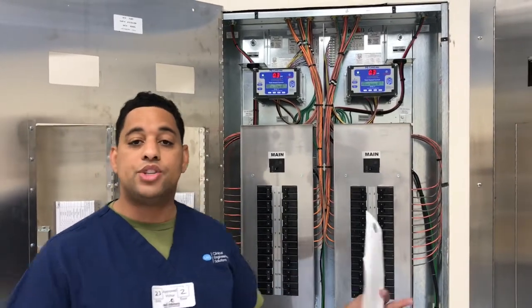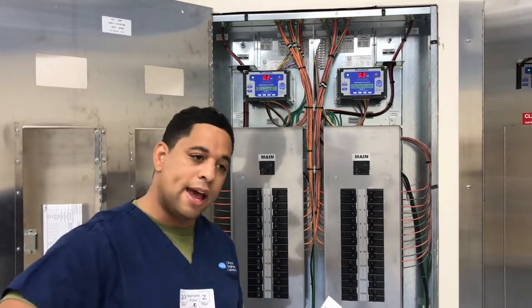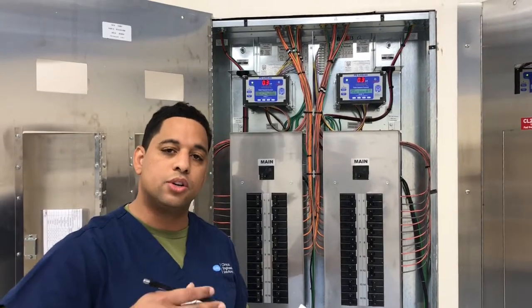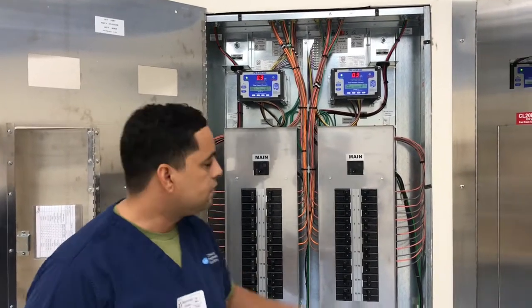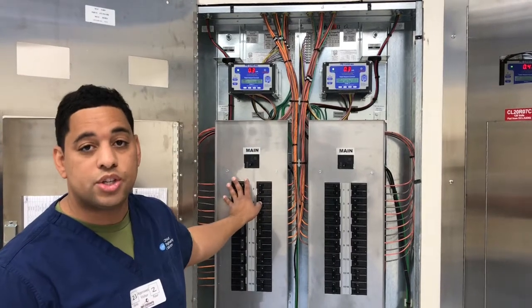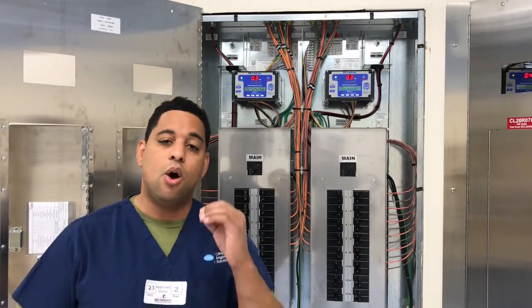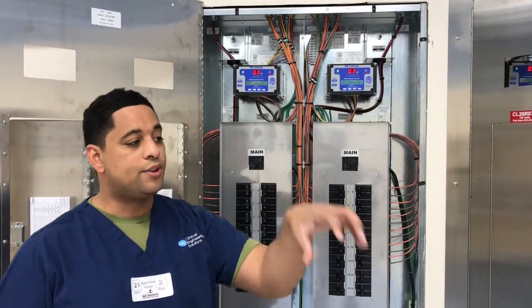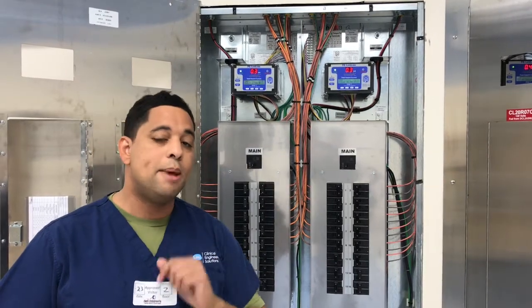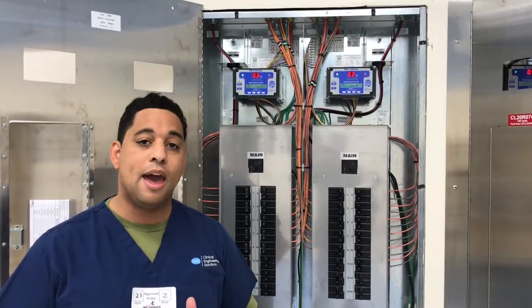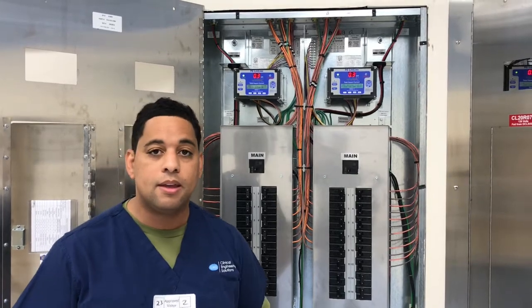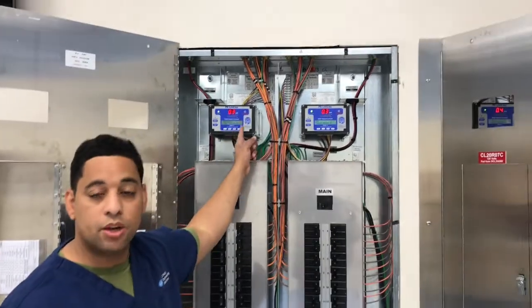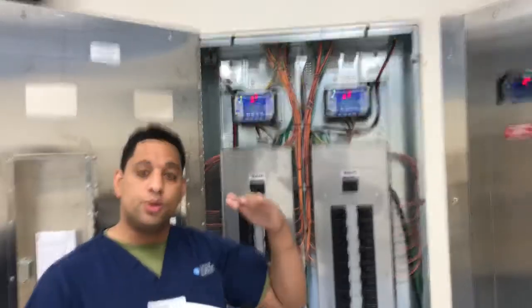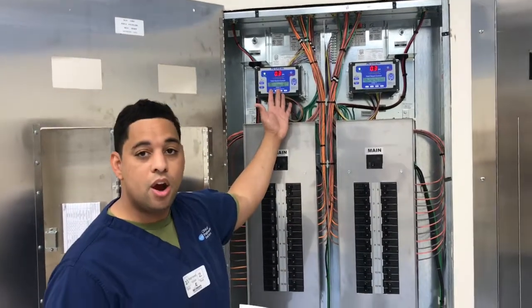And so that's how a GFCI works. It has a trip feature that shuts the power down. This does not. You don't want it to shut off. So the only way that the facility will know that a medical device may have a potential problem is when this alarms and goes off. Instead of losing power, it's going to alarm.